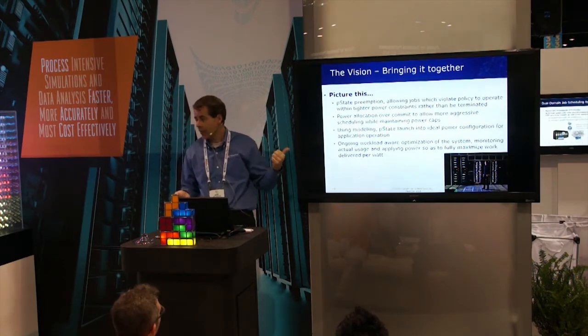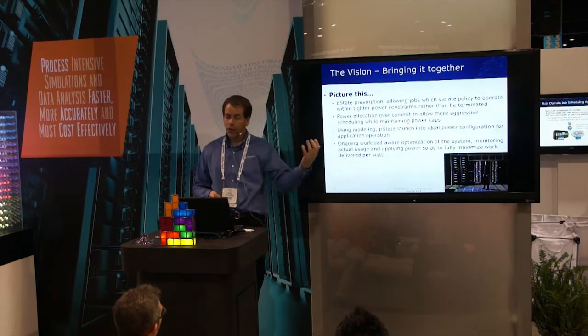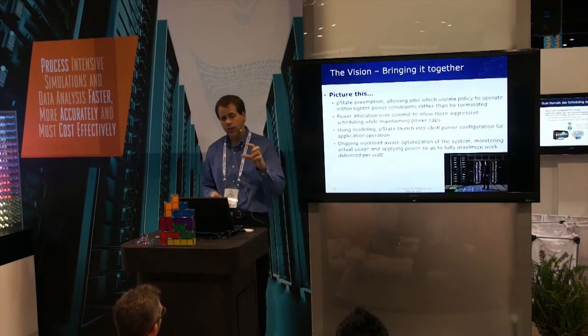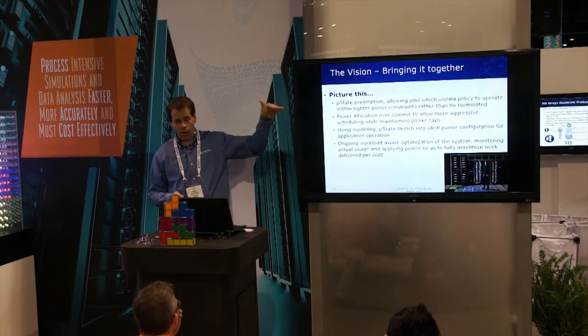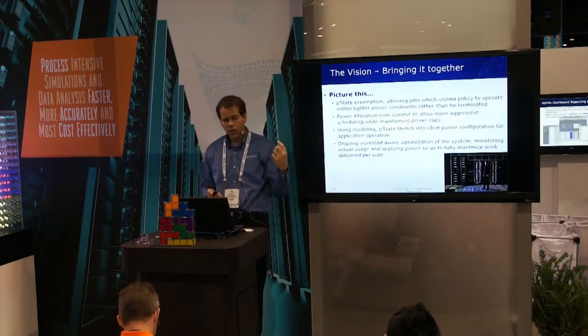Well, guess what? You don't have to cancel any job. You can actually say, I'm going to apply a P-state. I'm going to leave all my jobs that are running, I don't need to checkpoint them, but I'm just going to squeeze them down a little bit into a slightly tighter box. And then suddenly, I can be as aggressive as I want to be on my soft power budgets, because I know that if I do have to back off, it doesn't hurt very bad.